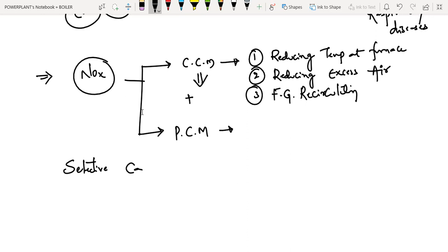In this method, NOx reducing agents such as ammonia are injected into the flue gas, and then this flue gas is passed through a catalytic bed, which results in the formation of less harmful products. That is, NOx compounds are reacted with ammonia, which is injected into the flue gas, and this mixture is passed through a catalytic bed. This will result in the formation of less harmful products such as nitrogen and water.